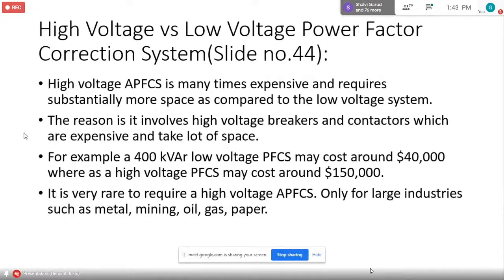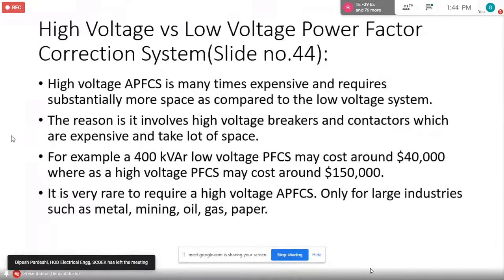but it was a smelter mine. Okay. High voltage APFC is many times more expensive and requires substantially more space compared to the low voltage system. The reason is it involves high voltage breakers and contactors, which are expensive and take a lot of space. For example, a 400 kVAr low voltage power factor correction system may cost around $40,000, whereas a high voltage system of the same capacity will cost around $150,000, so almost 4 times. It is very rare to require a high voltage system, only for large industries, as I told you.